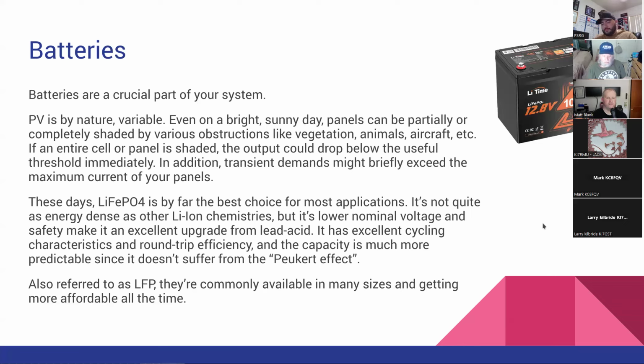The ratings you see on the sticker are almost always over 20 hours. So if you take the capacity of the battery and divide by 20, that means if you have a 100 amp hour lead acid battery and you drain 5 amps, then it's a 100 amp hour battery. But if you increase that to 20 amps, then you're talking C5 rate. There's a whole equation to figure this out.